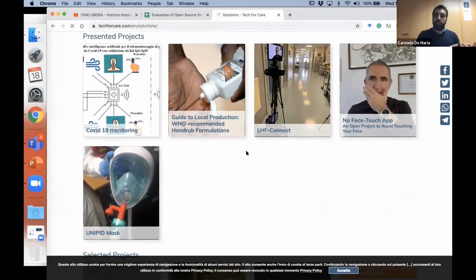In the moment of emergency, it was okay because it was mask or die. But after a few months, in which the situation is more stable, why don't we try to understand better how we can improve the device? And then other students, other researchers included an additional valve to balance the pressure.